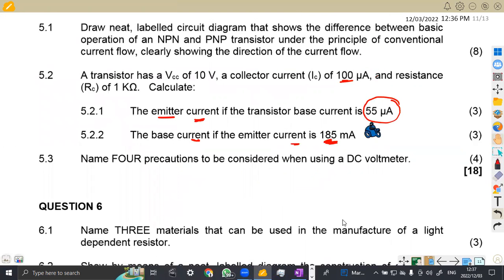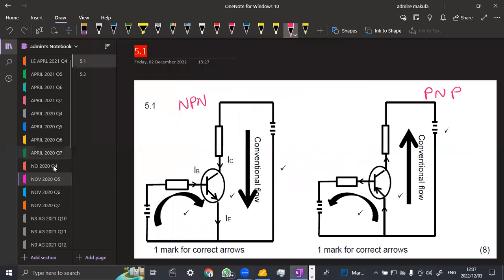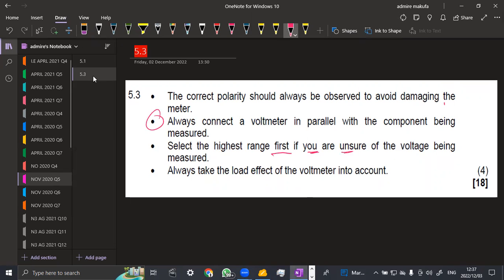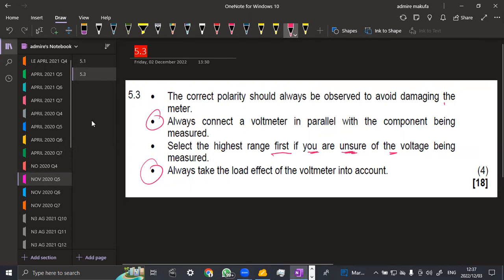Name four precautions to be considered when using a DC voltmeter. The correct polarity should always be observed to avoid damaging the meter. Always connect the meter in parallel with the component being measured. Select the highest range first if you are unsure of the voltage being measured, then reduce to a lower range. Always take the load effect of the voltmeter into account.